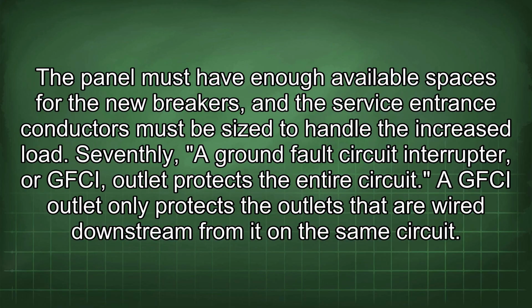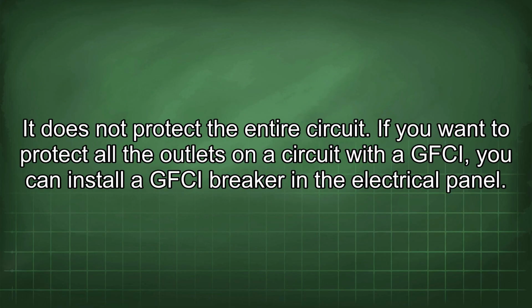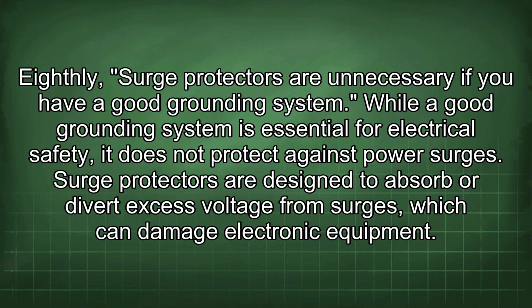Seventhly, a ground fault circuit interrupter, or GFCI, outlet protects the entire circuit. A GFCI outlet only protects the outlets that are wired downstream from it on the same circuit. It does not protect the entire circuit. If you want to protect all the outlets on a circuit with a GFCI, you can install a GFCI breaker in the electrical panel.